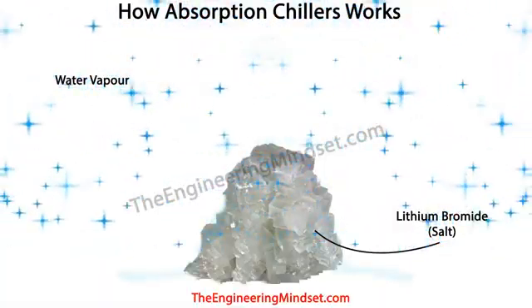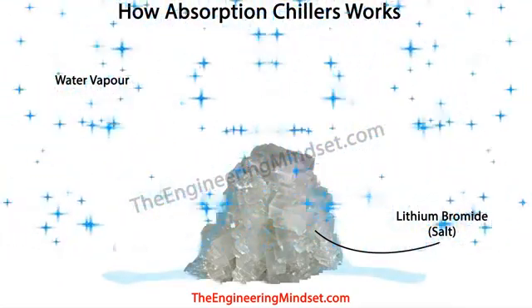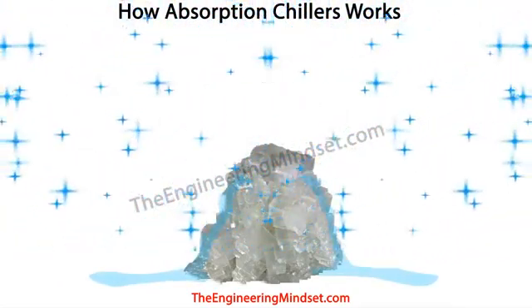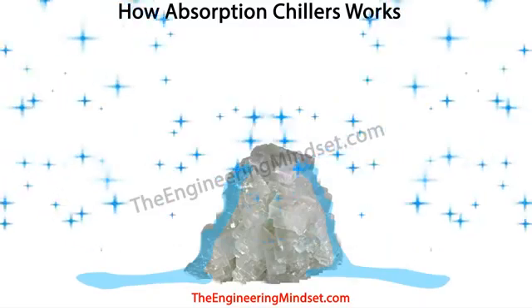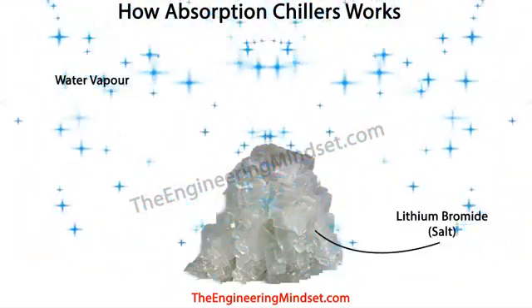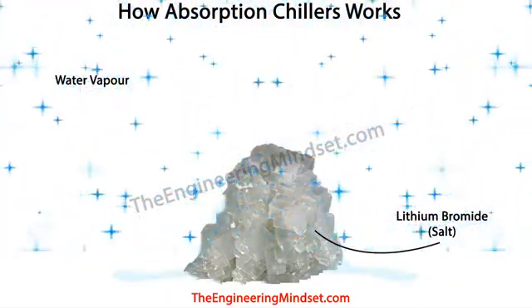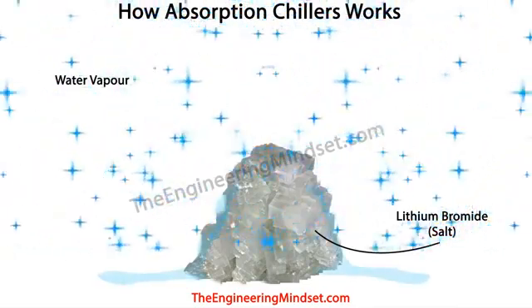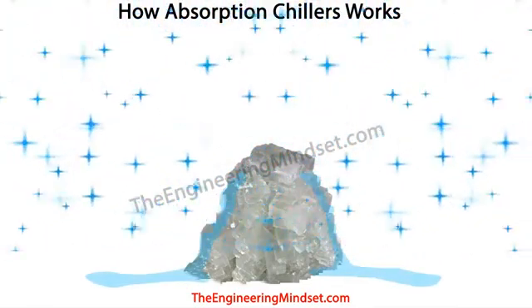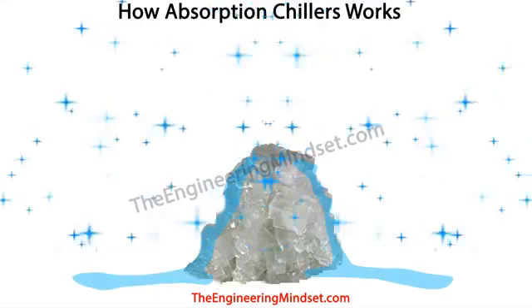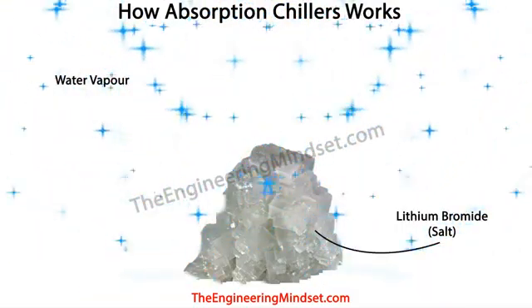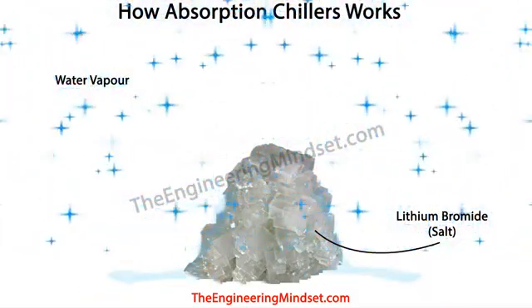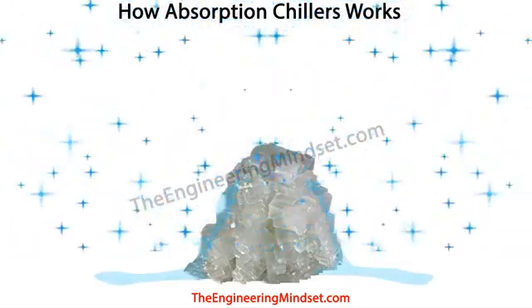The second thing to understand is that lithium bromide is a salt, just in a liquid form. And salt is attracted to water moisture. It literally pulls these particles of moisture out of the air and is attracted to it almost magnetically. So if we spray lithium bromide onto some water vapor, then the two will be attracted together and will join.